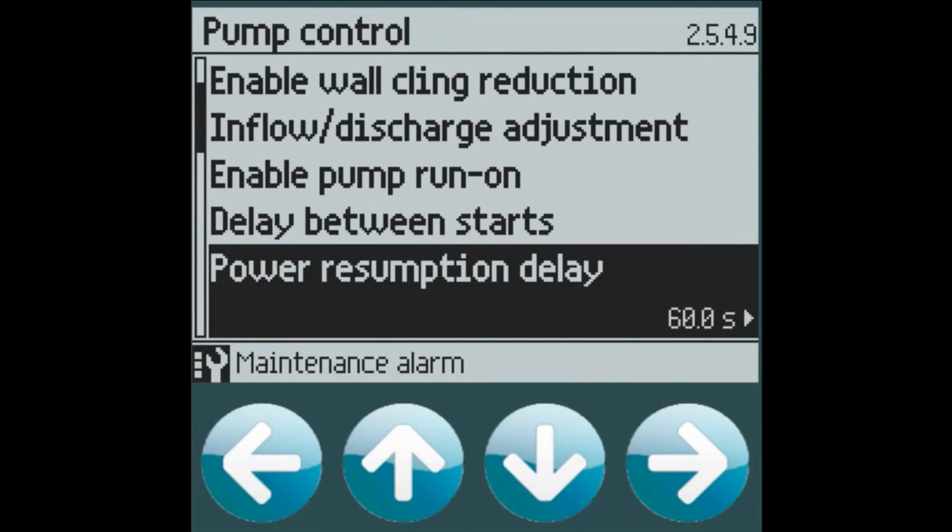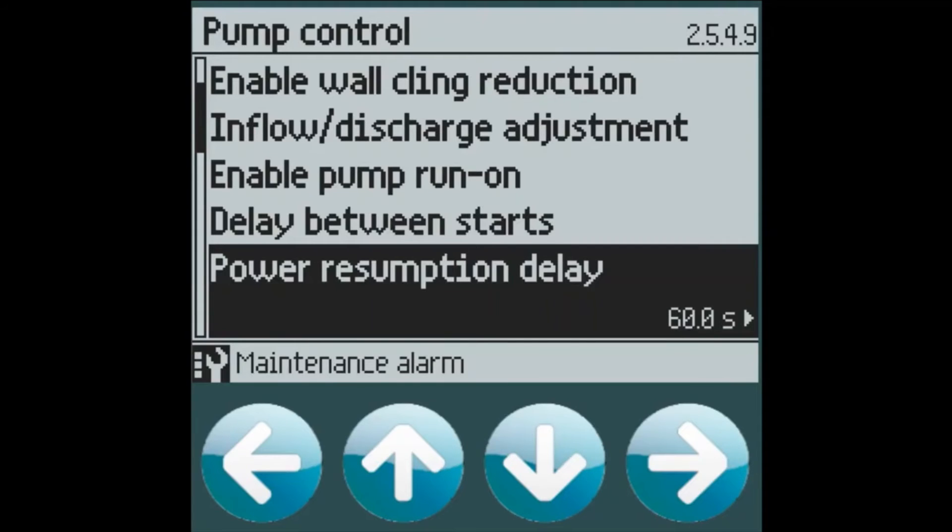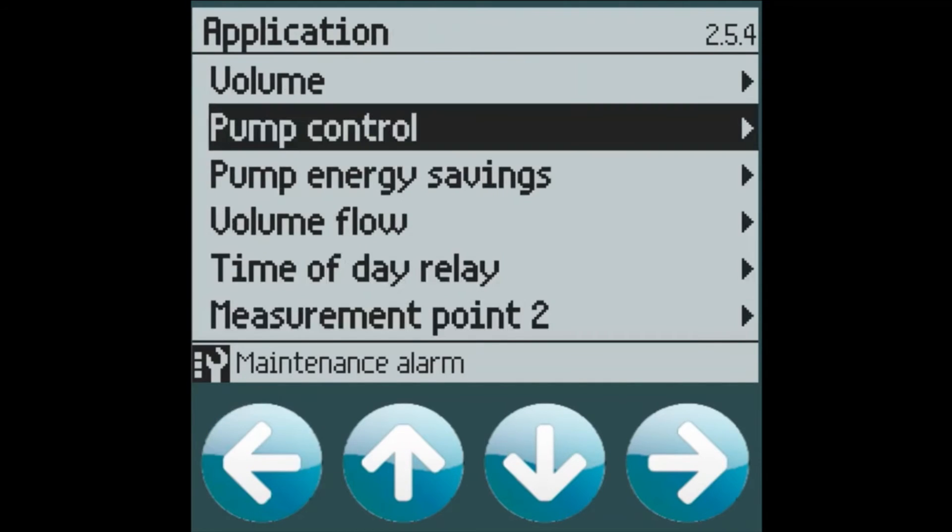We can also do a power resumption delay, which means that we will hold off on turning any pumps back on if power is lost to the device. And as everything is coming back on, we don't want to overload those circuit breakers. So we can put in a delay upon power being reapplied to all the equipment at the site.